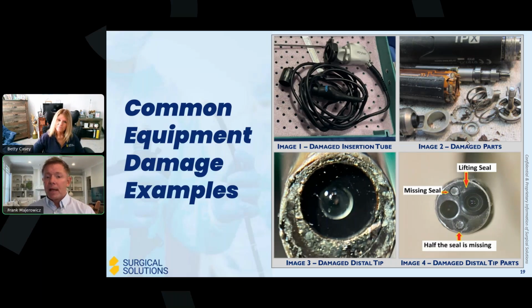Hard to tell what that might be, but that is actually a magnified view of the distal tip of a rigid endoscope. Okay, you can see all around the edges. That's a combination of, and this is what makes this such an interesting photo, a combination of things going on here: laser damage from laser burns, and actual metal damage from a shaver that was utilized during a procedure that was not far enough away from the tip when it was activated, causing this type of damage to the tip. Now, to the naked eye, it might not look this bad, but again, under magnification, you can truly see how not handling the equipment properly, following the correct IFUs, what type of damage it can cause to a scope.